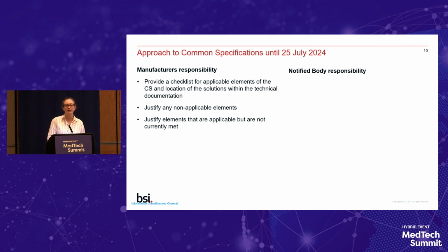So for example, for HIV, you're meant to test 400 positive HIV-1 patients. So we ask for the precise location of where the data for those 400 patients is, and we make sure that it adds up to 400 as well. The manufacturer is responsible to justify any non-applicable elements because the common specifications are written for general devices. It doesn't always meet those specifics depending on the device design and manufacture and intended purpose. Not every element of the common specification is appropriate for every device.